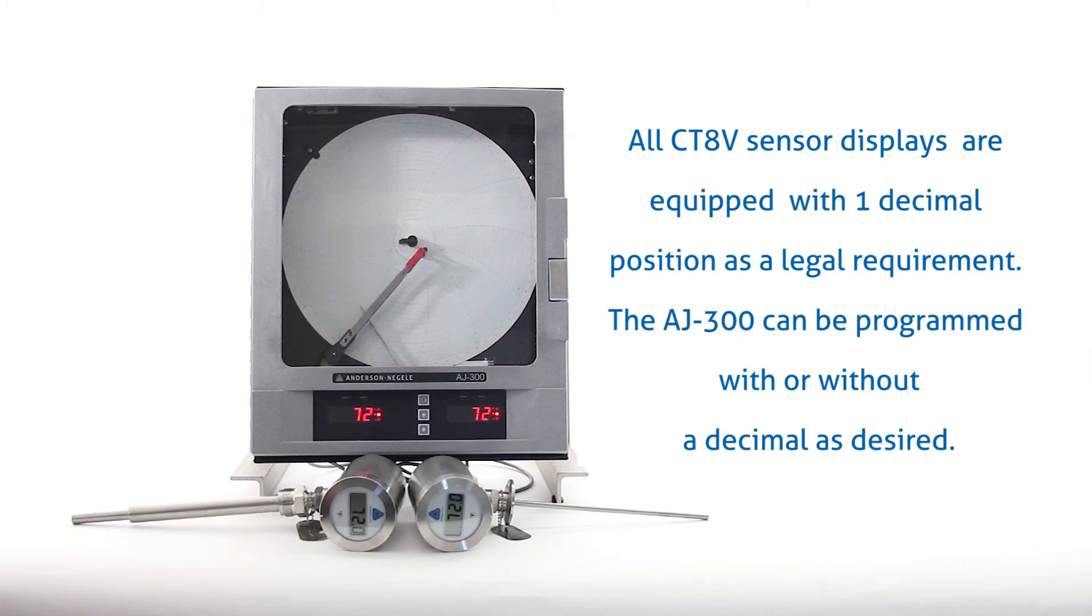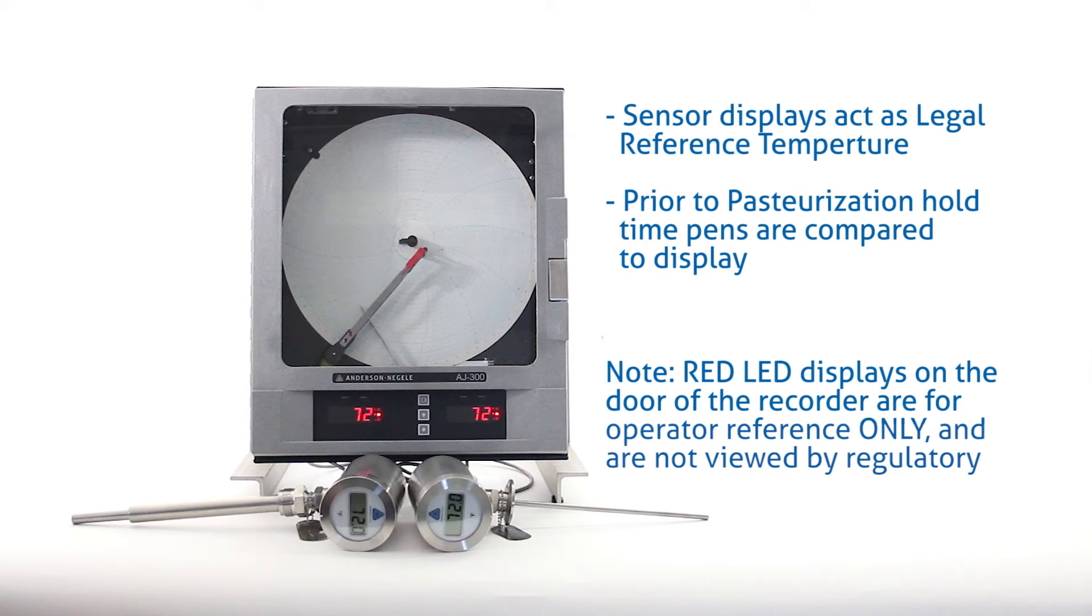All CT8V sensor displays are equipped with one decimal position as a legal requirement. The AJ300 can be programmed with or without a decimal as desired. The display on each of the sensors acts as the legal reference temperature for the system.